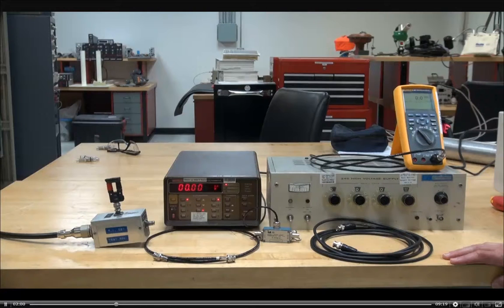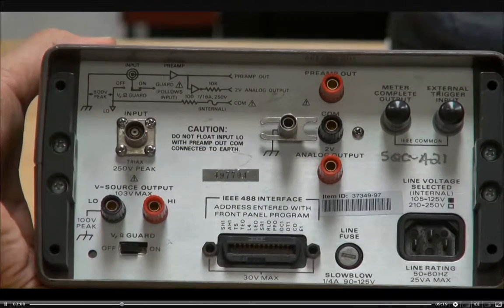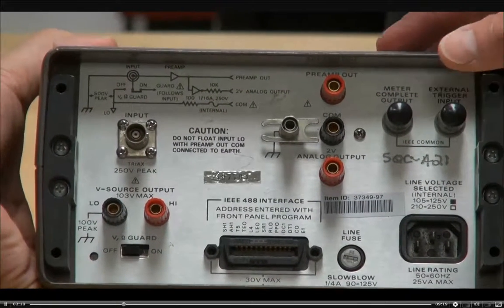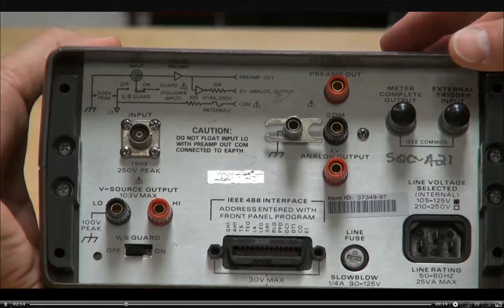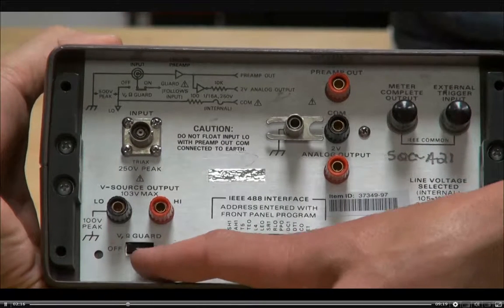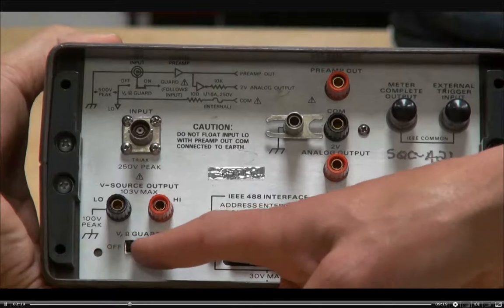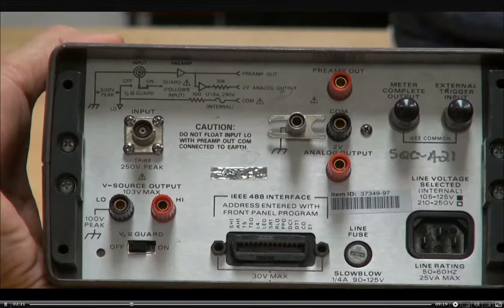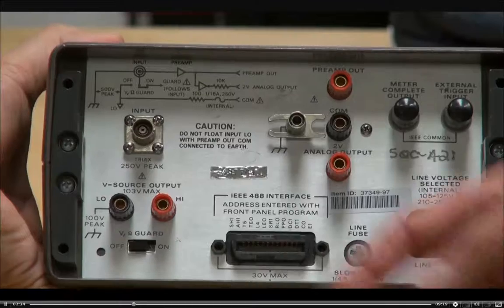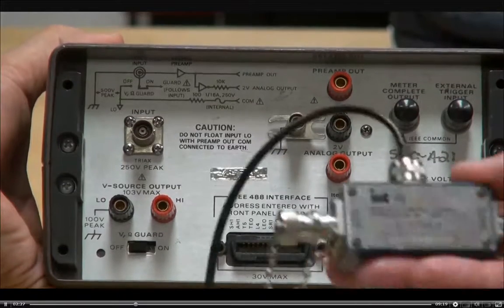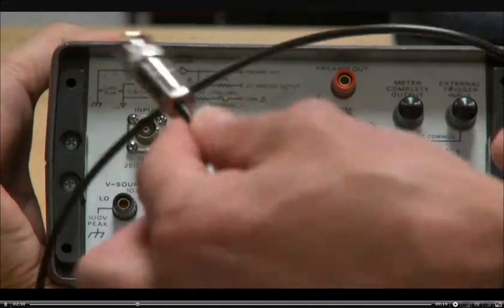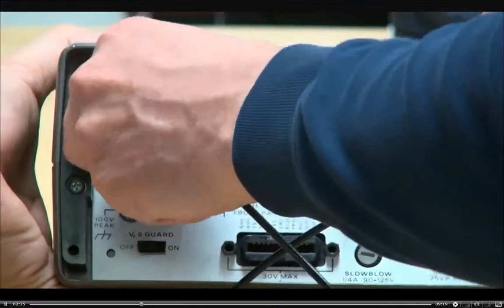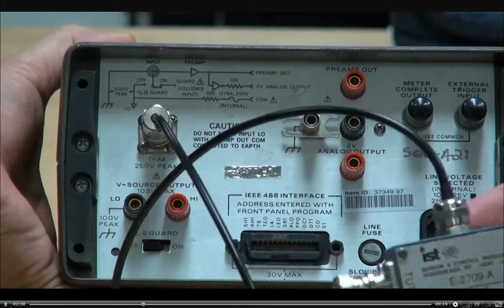Okay, we've already talked about the volts ohm guard switch on the rear panel is set to off. Part of the setup for the electrometer is it asks you to place the volt ohm guard switch on the back panel to off. So right here it is, volt ohm guard. It is to the left, to off. And the other thing that you need to know on the back of the electrometer is the input. So when we're using our little blue test box here, the cord that comes out the top of that test box is the input that goes into the back of the electrometer. So that's the connections on the back of the electrometer.